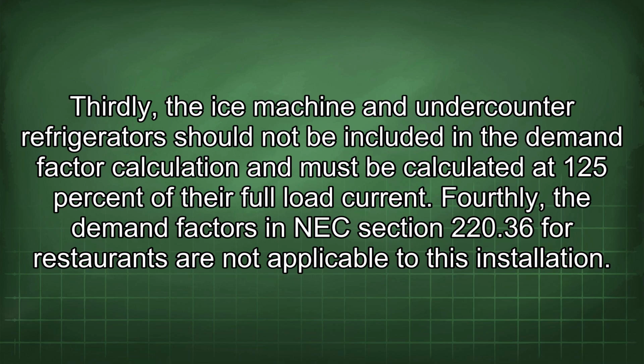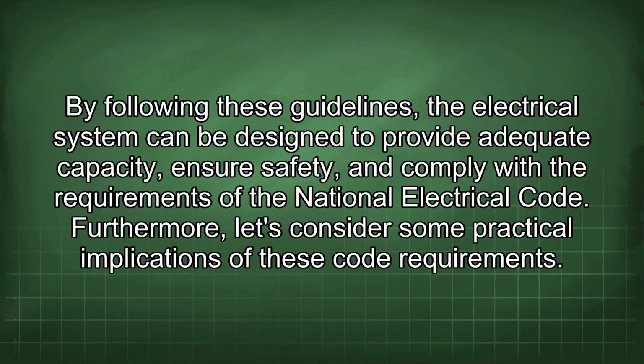Thirdly, the ice machine and under-counter refrigerators should not be included in the demand factor calculation and must be calculated at 125% of their full load current. Fourthly, the demand factors in NEC section 220.36 for restaurants are not applicable to this installation. By following these guidelines, the electrical system can be designed to provide adequate capacity, ensure safety, and comply with the requirements of the National Electrical Code.